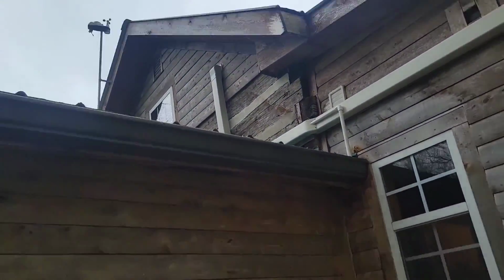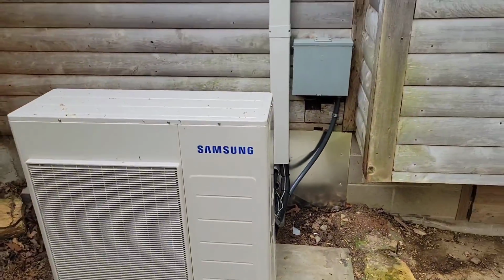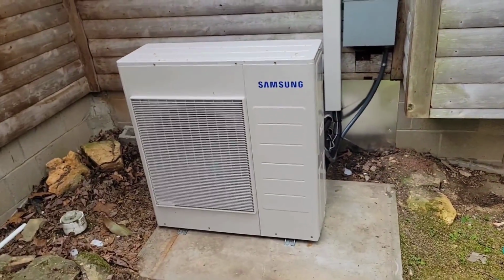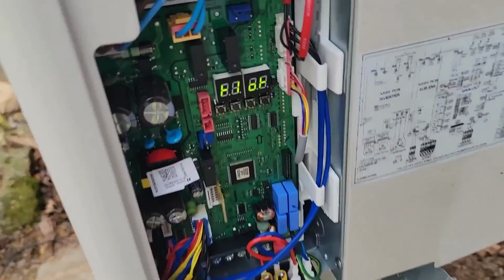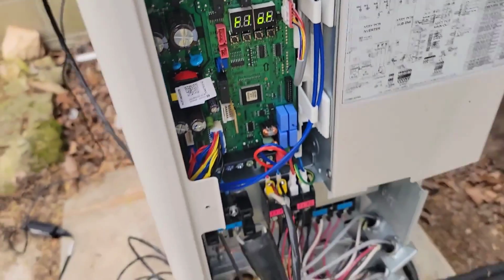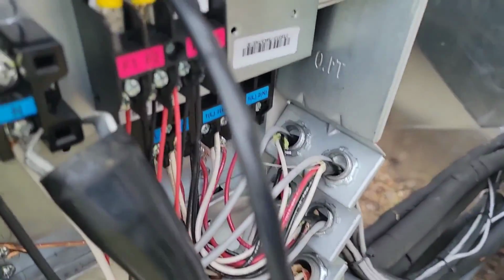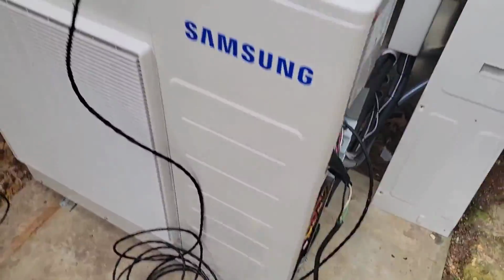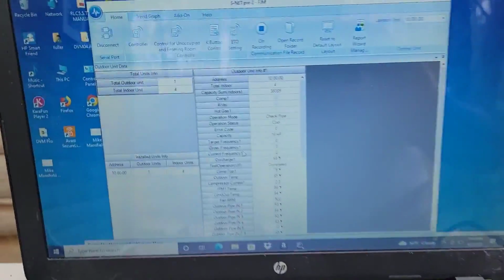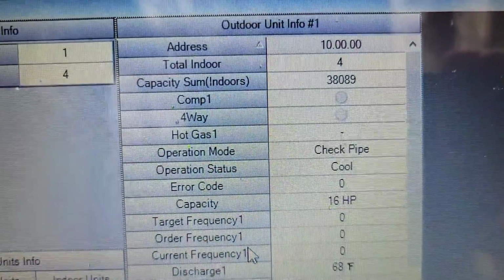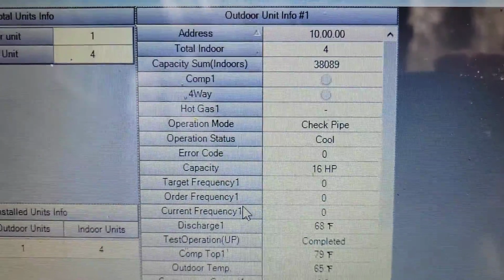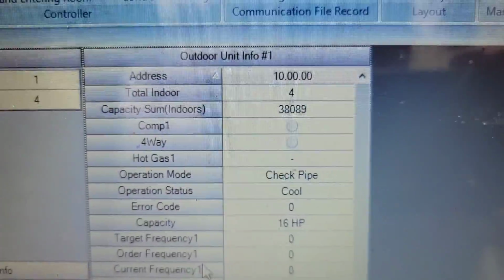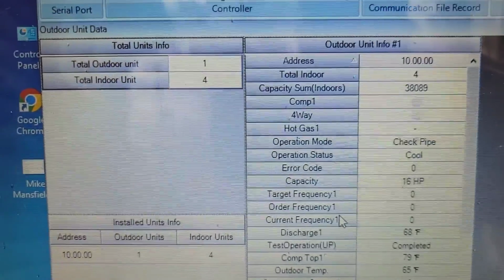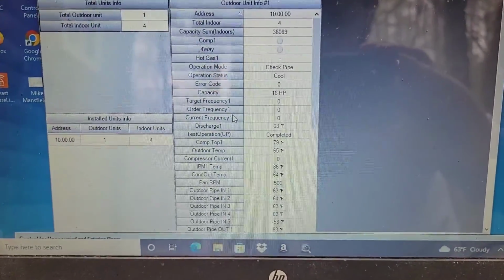Line hide cover, looking good. Okay, got the SNet tool and SNet Pro software connected to the F1 and F2. We're in pipe check operation. It says operation mode, check pipe. Got 4 total indoor units, capacity sum for the indoors, and 1 outdoor unit.